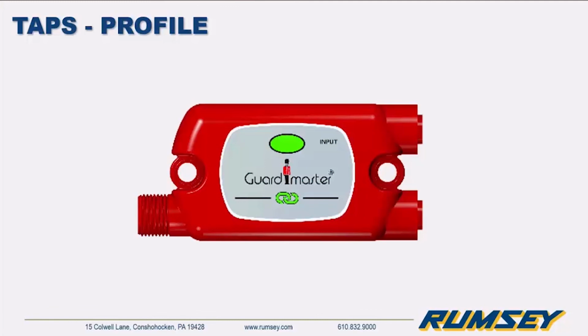Like I said, you're essentially going to have multiple devices connected in series. So you're going to have an M12 cable coming in one side and an M12 cable going out the other side, the exception being the last tap, which would have a shorting plug on the end, and that allows the system to know that that was the last tap. The bottom LED shows continuity of the chain, so if a device that is not connected to a specific tap trips, that bottom LED will flash red, letting you know that there has been a break in the chain, but also that it is not that specific device. That can help you diagnose which tap tripped, which device tripped, as opposed to having to walk around your machine or your plant and try to eyeball it, saving you some time in diagnosing the issue.